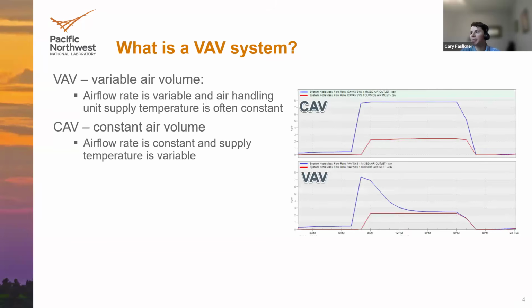So this is kind of an example of what those airflow rates could look like, where that top plot just shows more of a constant air volume system. There might be some ramping when you turn the fan on and getting the system moving initially, but it's just going to be more of a constant flow rate. Whereas then on the bottom, you have the VAV system, which might modulate the airflow in order to meet the heating or cooling demands.